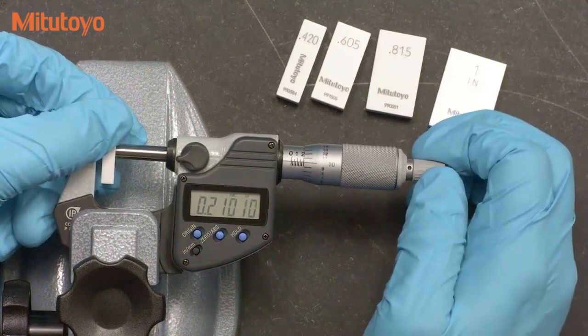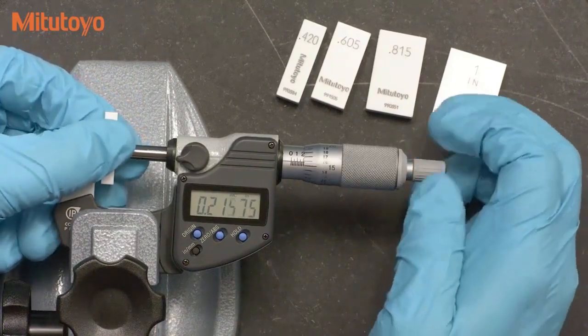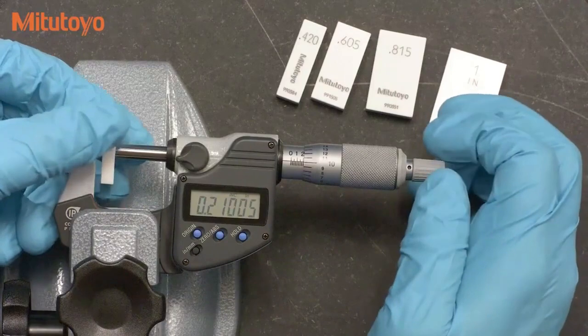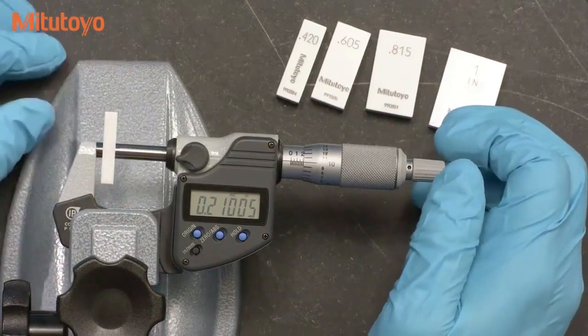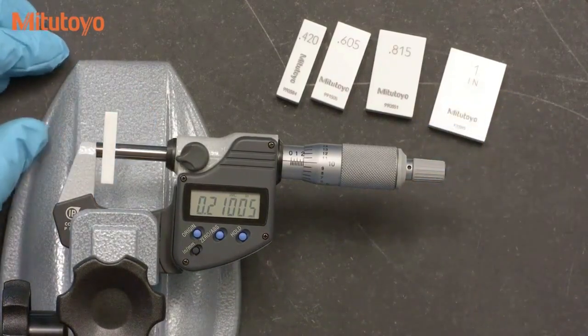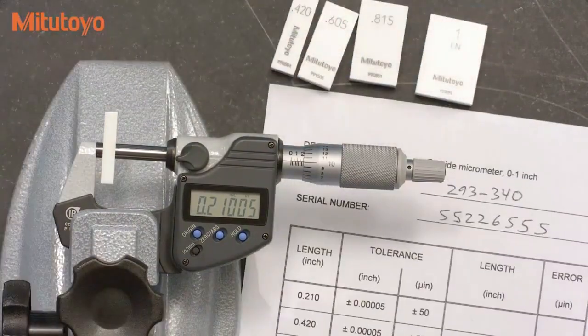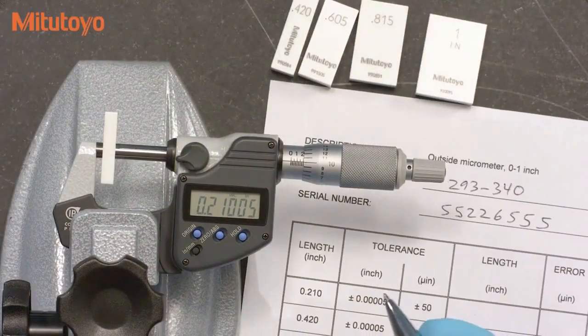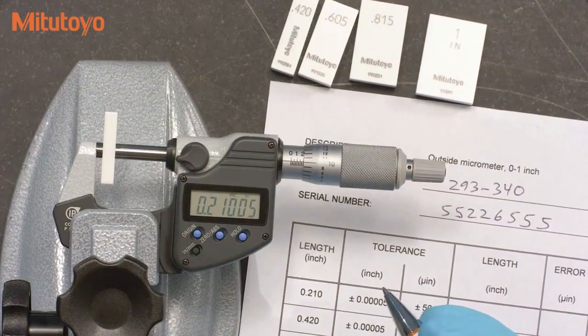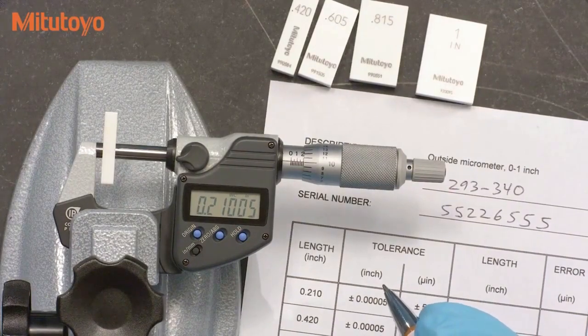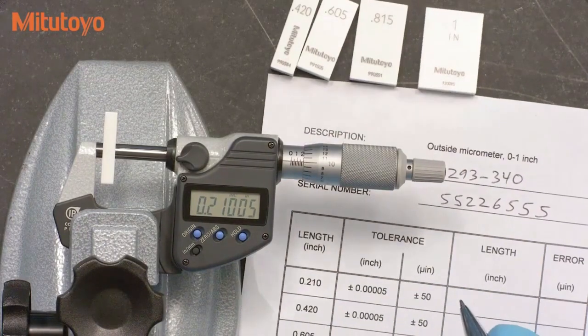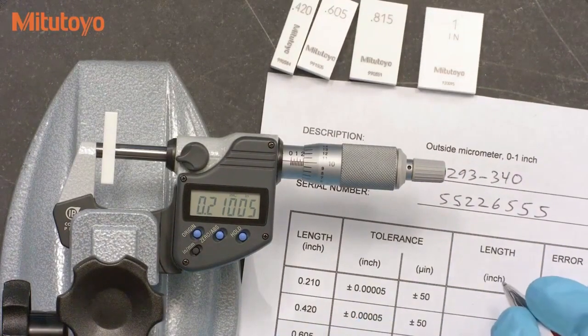It's common to take a few readings with the goal to ensure that you have a consistent value. This is typical practice when using a micrometer. It is not correct, however, to take a bunch of readings and report the average during the calibration. The micrometer should repeat within the specification limits for the length accuracy, and if not, then you should reject the micrometer. The reported error is the measured value minus the value of the gauge block.